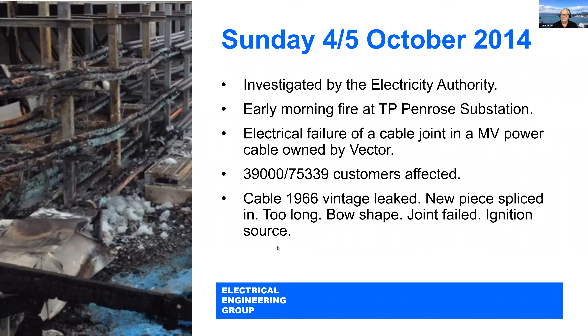Neither Transpower nor Vector identified the trench fire as a risk, according to the Electricity Authority report, and 38 cables, including control cables, were damaged. The picture on the right shows how the cable layout was at the time. They started off with far fewer cables, but as time went on, new services had to be added, so the trench was quite full, and the fire propagated to cable racks above ground.